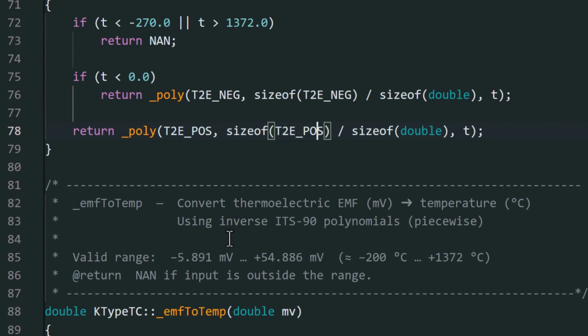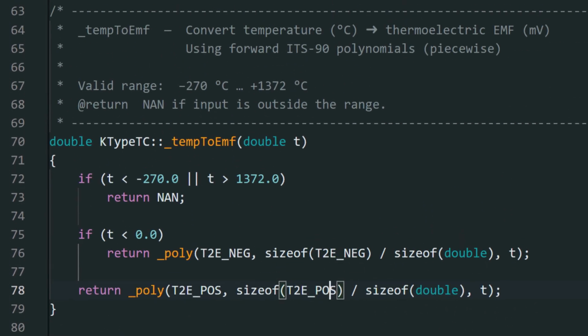Then we have our two functions that do temperature to voltage and voltage to temperature. Why do we need the first one? That's for the cold junction compensation. First, it checks the range to make sure you're within range. If not, it returns not a number. If your temperature is negative, that tells you to use this array, and you can see we're calling our polynomial function. This double T is our input temperature, once again from the cold junction compensation.